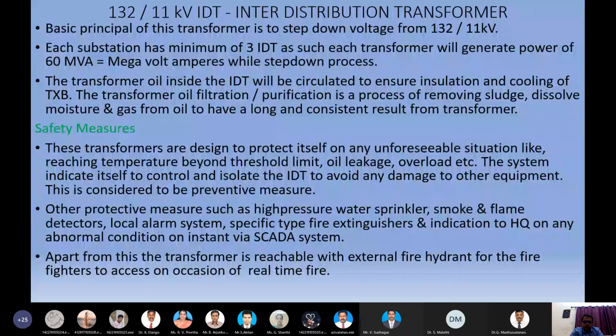The other protective measures, such as high pressure water sprinklers and smoke detectors, are called protective measures. The internal design of the transformer, we say, is a preventive measure. The other protective measures such as high pressure water sprinklers, smoke and flame detectors, they will have either smoke or flame, depending upon the geographical conditions and the place where the substation is located. Because we have substations inside the countries, inside the states, inside the cities, and outside the countries, outside the cities. So depending upon these areas, the flame or smoke detectors might differ. And a local alarm system is common.